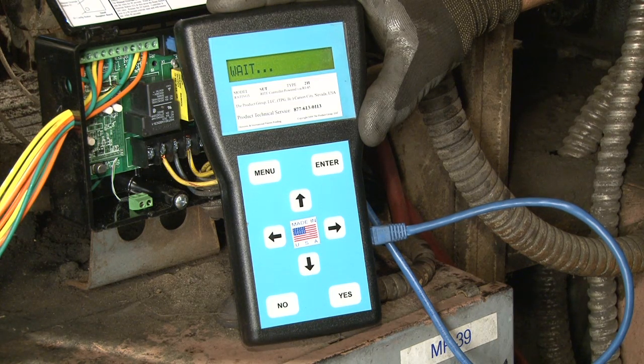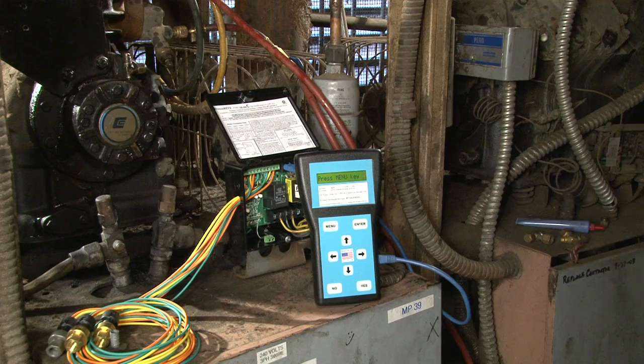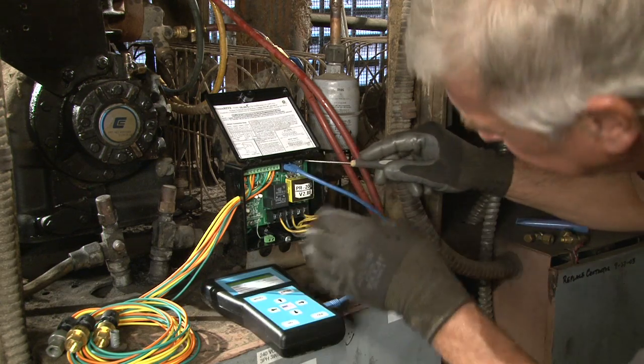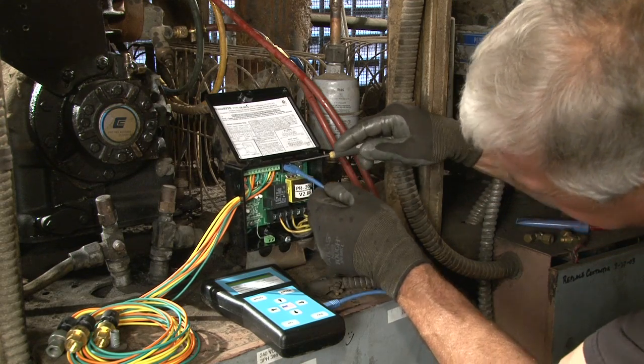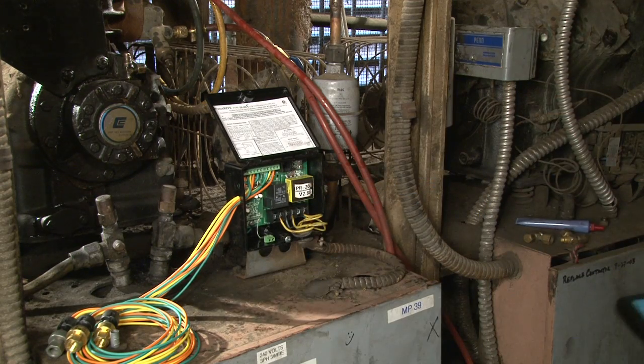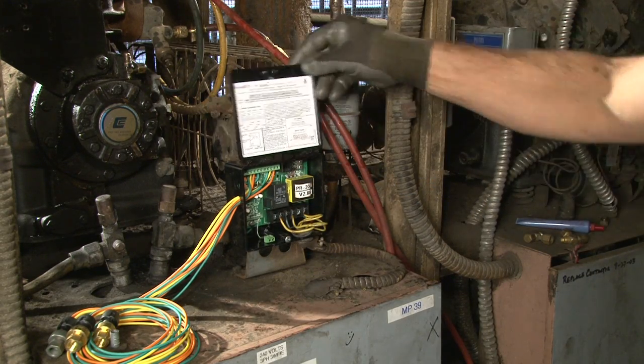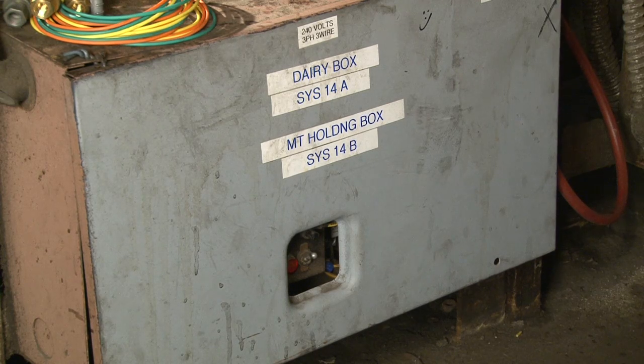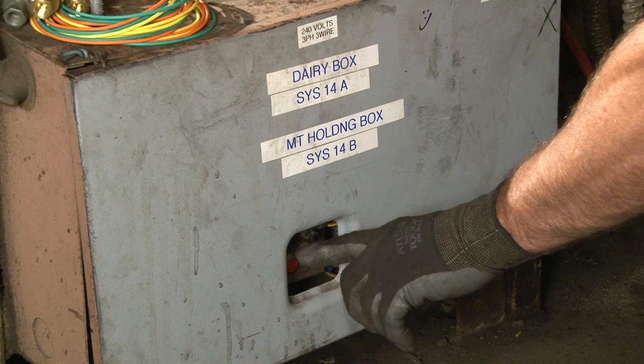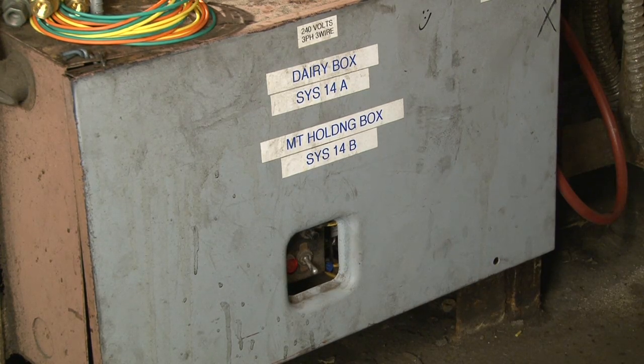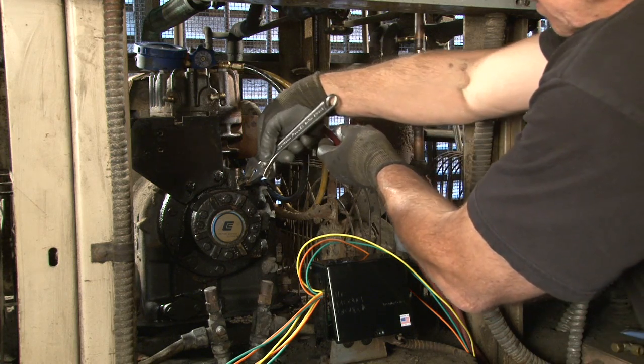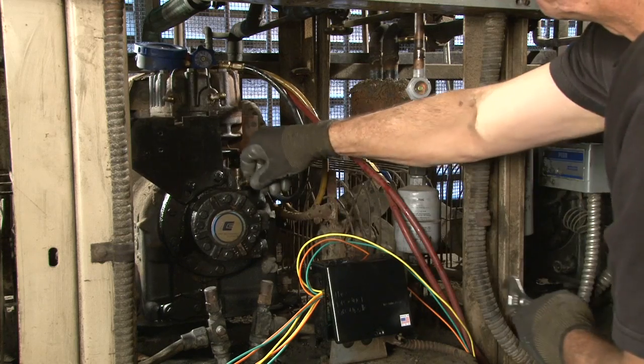This calibration process takes but a moment. It has now calibrated all 3 transducers to properly work with the PressuRITE controller and the compressor system. Next, he removes the setup tool from the PressuRITE controller, closes the cover, and turns off the control power. This ensures the compressor will not start inadvertently.